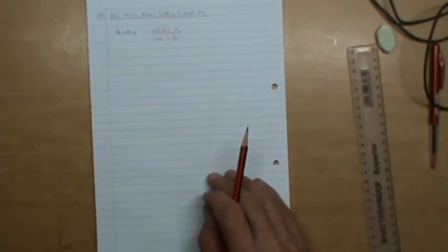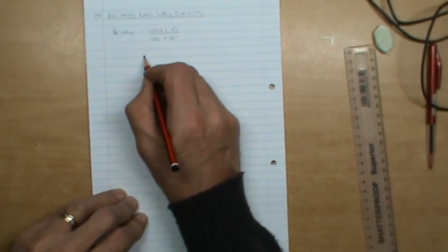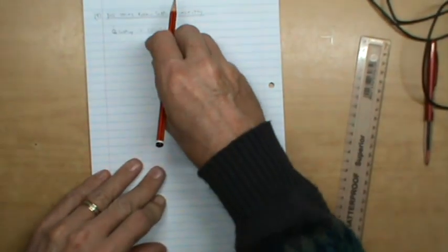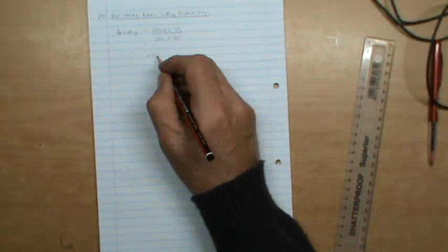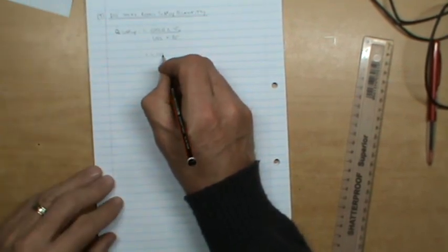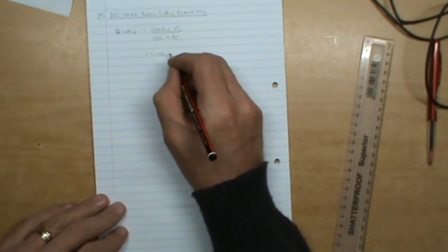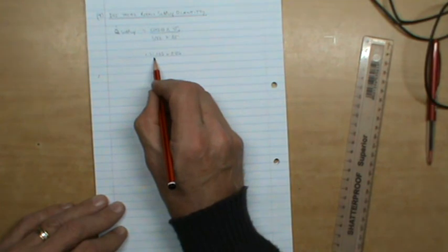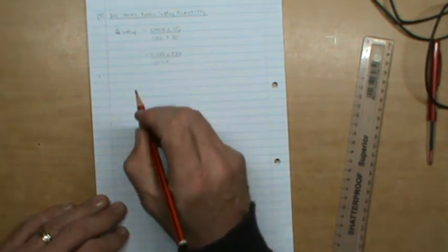Right, so then we find out that our volumetric flow into that area is going to be equal to the effective room sensible heat, which was 21,035, times this particular volume that we've just worked out, which is 0.816, divided by 1,012 times delta T, and we said delta T was 12,32.